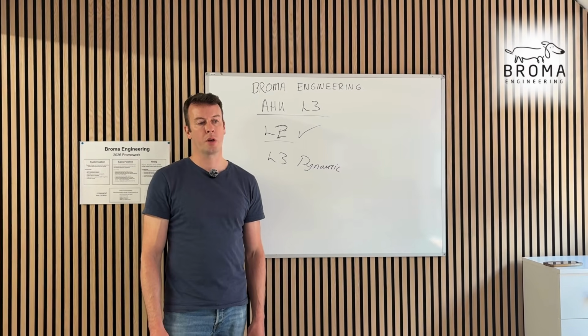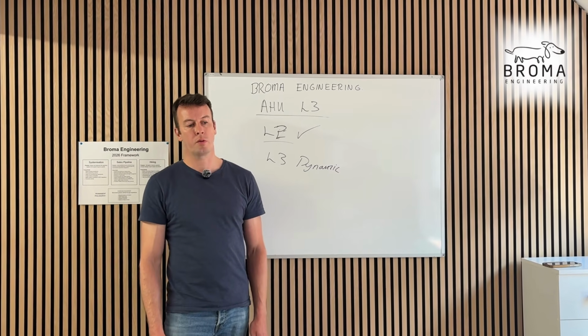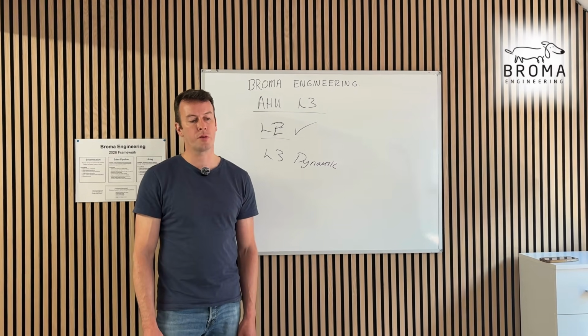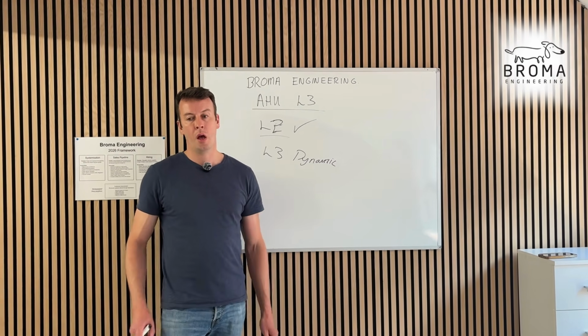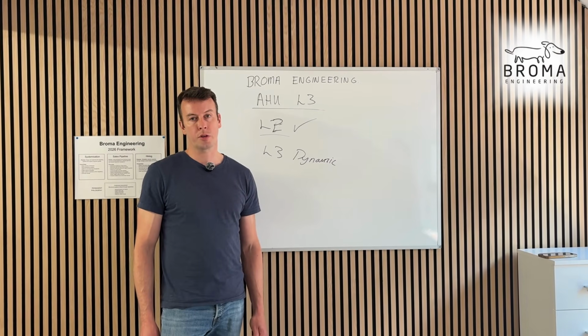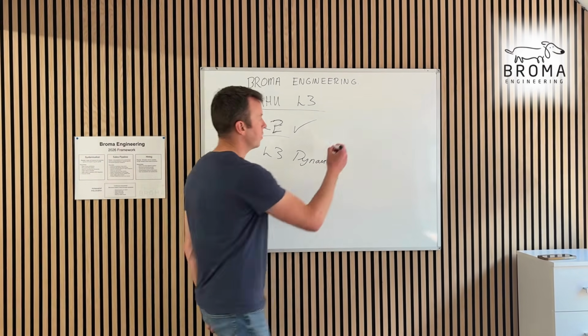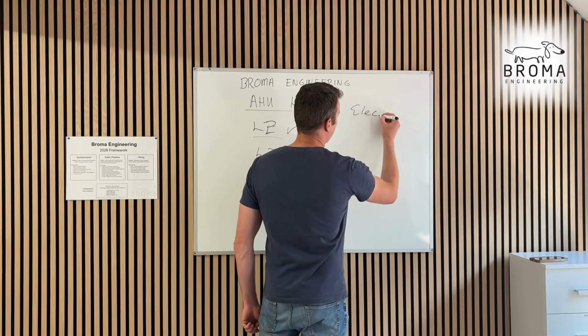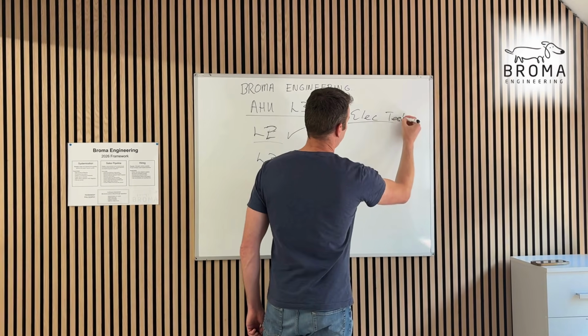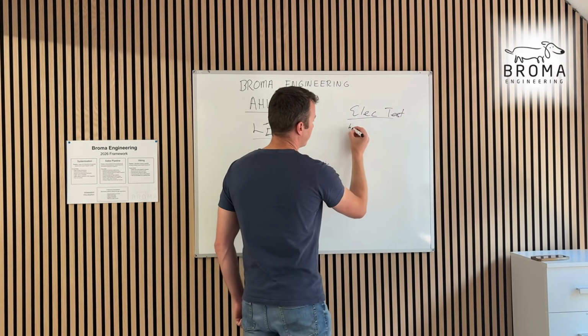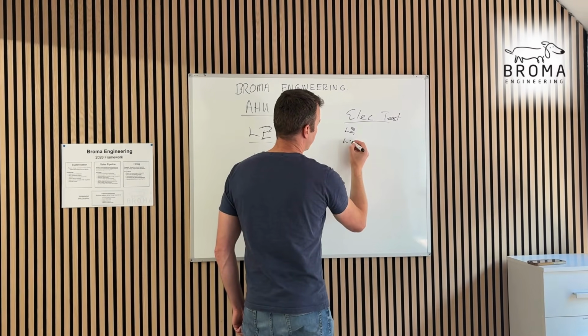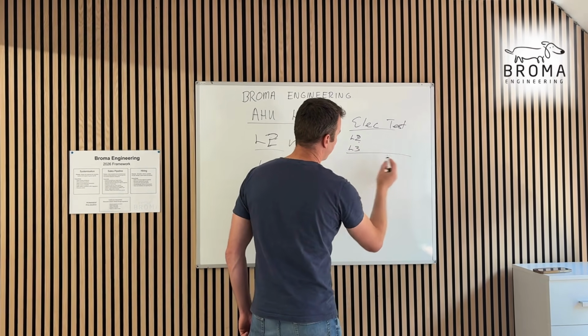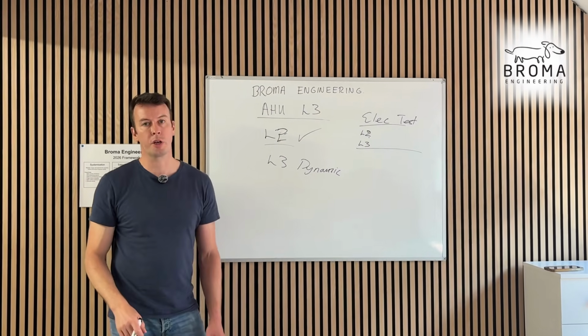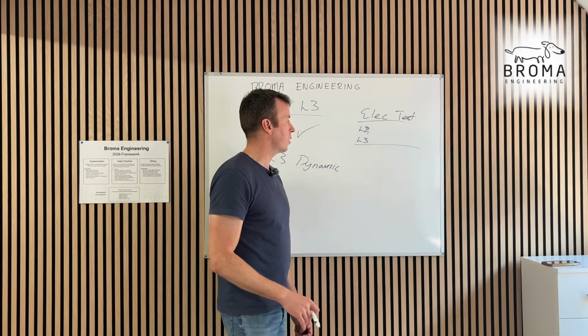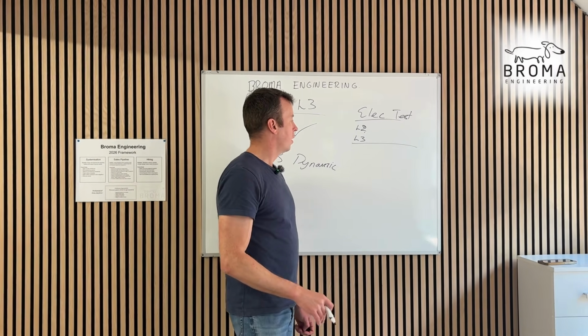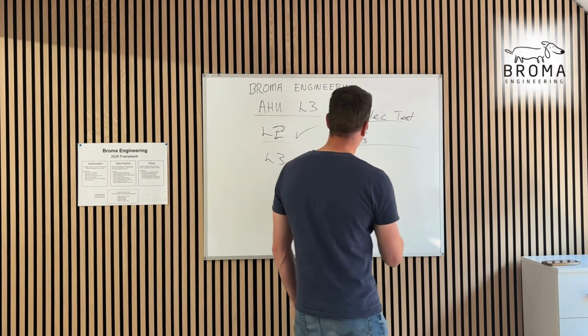So power is on, checking all the electrical tests that we have to do - they'll be in the scripts. I'll just cover what you check: your phase rotation, check voltage between phases. All that will be in your level 3 electrical check, that's for the electrical testing only. So usually you have your electrical test sheet, and you'll have your level 2 stuff, and then your level 3 stuff on the same page, and that'll be your entire electrical check for those cables. So you're covering the cables, and you're covering voltage, earth fault loop impedance testing, and all that.